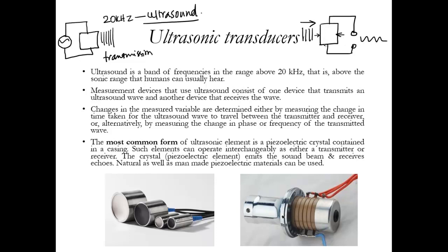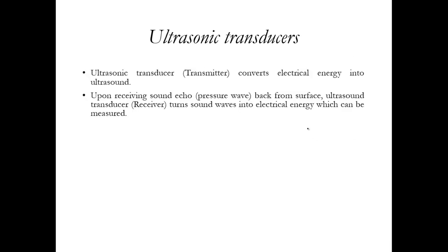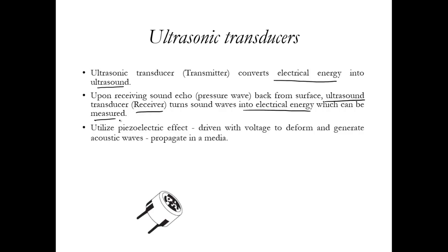So all these ultrasonic transducers mainly employ piezoelectric materials, piezoelectric crystals, as their basic component. They convert electric energy, in the form of excitation, into ultrasound, or mechanical energy in the form of sound waves. At the receiver end, this mechanical energy is converted back to electrical energy, which can be measured, displayed, or used for control purposes. So the piezoelectric effect is being used, which uses voltage to deform and generate the acoustic waves.